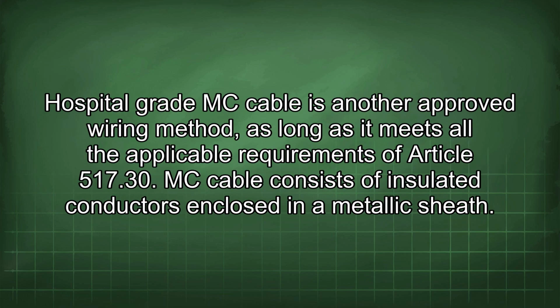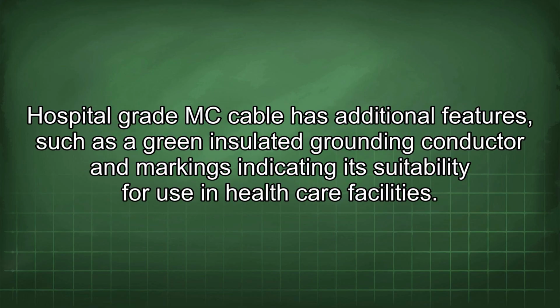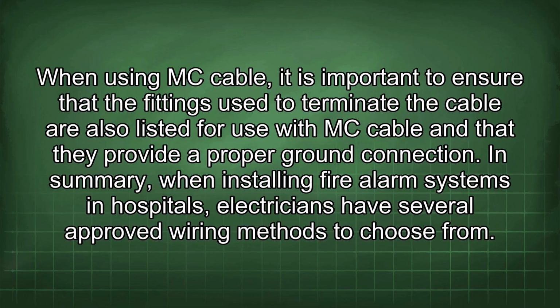Hospital-grade MC cable is another approved wiring method, as long as it meets all the applicable requirements of Article 517.30. MC cable consists of insulated conductors enclosed in a metallic sheath. Hospital-grade MC cable has additional features, such as a green insulated grounding conductor and markings indicating its suitability for use in healthcare facilities. When using MC cable, it is important to ensure that the fittings used to terminate the cable are also listed for use with MC cable and that they provide a proper ground connection.